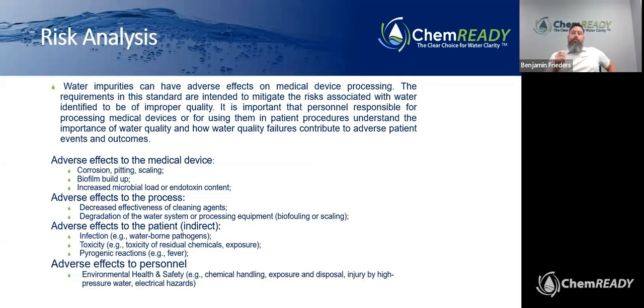So that moves us to the risk analysis. Most facilities should start this step to identify what it is that they need to do to be compliant with ST108. So the reason that we are doing this risk analysis is the whole point of the standard is that water impurities can lead to surgical site infections. The whole reason that AAMI developed the standard is to minimize the possibility of surgical site infections because of medical devices. So they have recognized that impurities on those medical devices can have adverse effects.